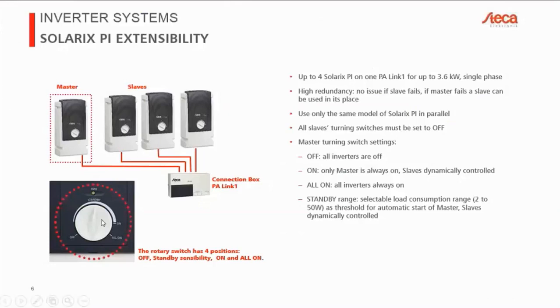So let's look at the possible positions for this turning switch. I've already mentioned that for the slave, all of the switches must be turned to the off position for safety reasons. Now, what about the master? The good thing about the system is that we only need to worry about one turning switch. All of the other ones should always stay off. The master is the only one that we need to control. So we have 4 positions here. We have an off position on the very left, an on position on the right, and on the bottom right, we have all on. These 3 conditions are quite simple to explain.